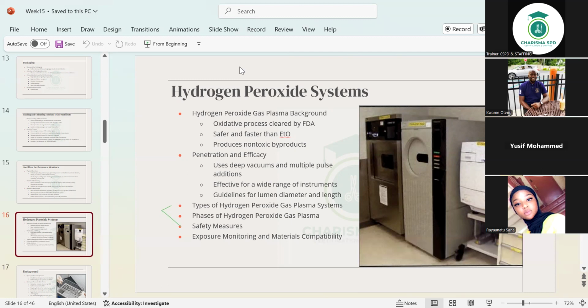When you go to the sterilizer machine and open it, it tells you the electrodes may be hot. And the electrodes are not anything complicated. They are more like, how should I define it, some basket stuff in there, like some woven metal. But it always cautions you that when you open it, those electrodes may be hot. So be careful unloading the stuff. So this is one of the things that it uses, that the RF energy ionizes the hydrogen peroxide, creating hydrogen peroxide gas plasma.